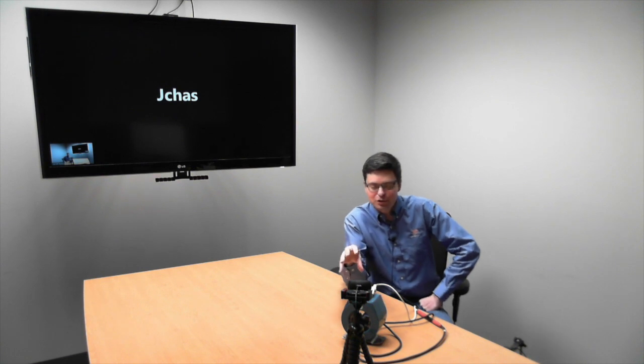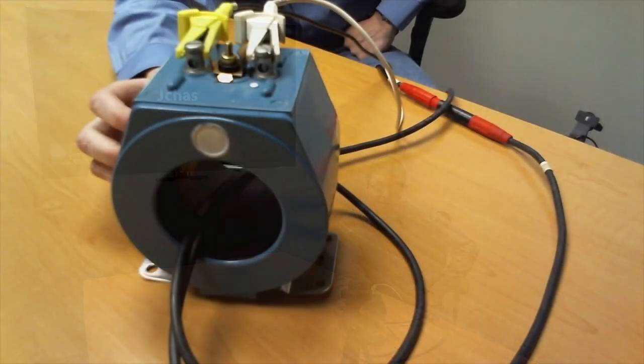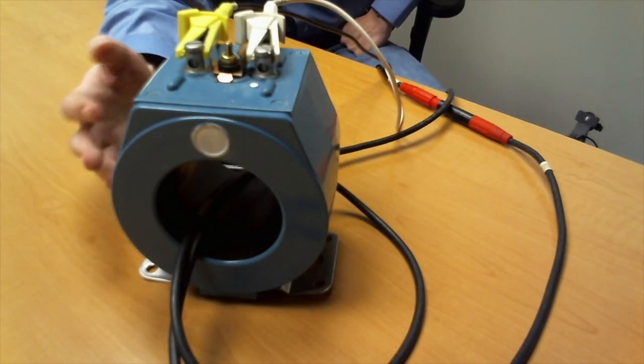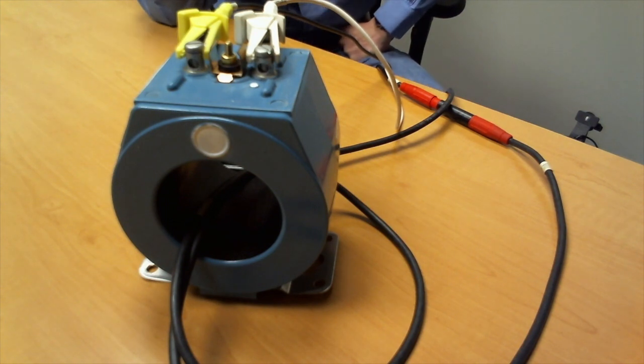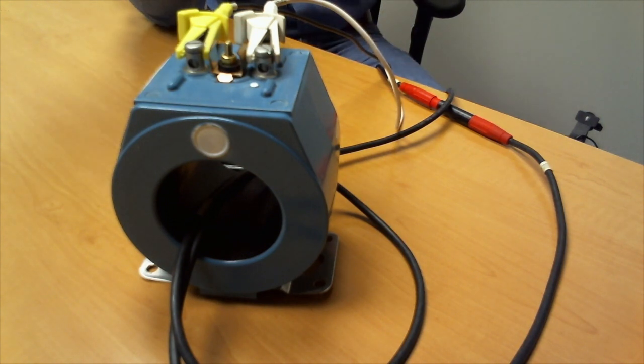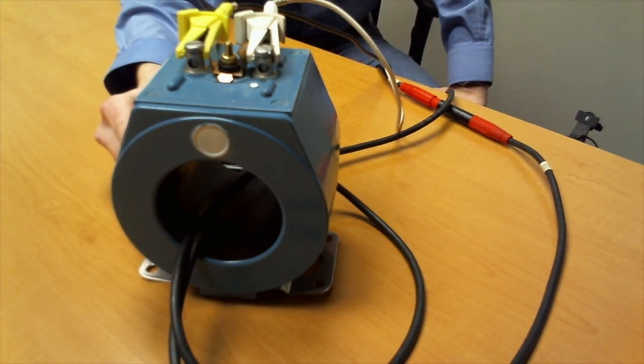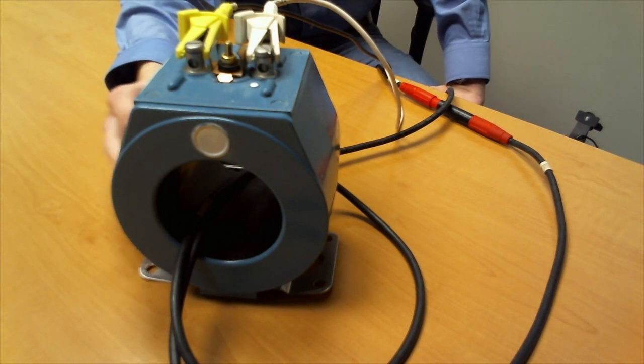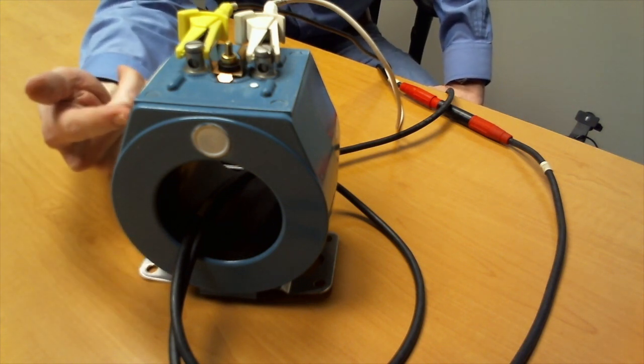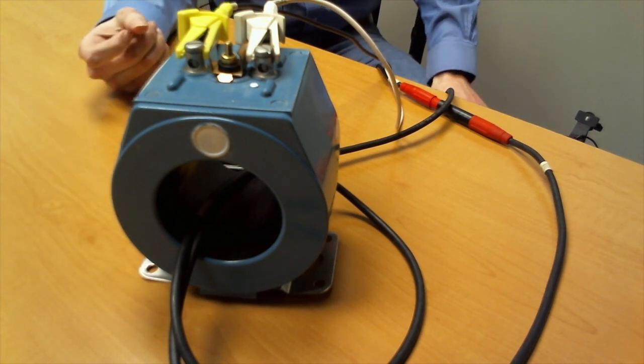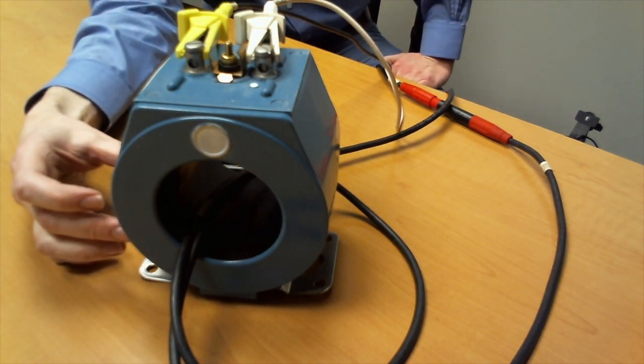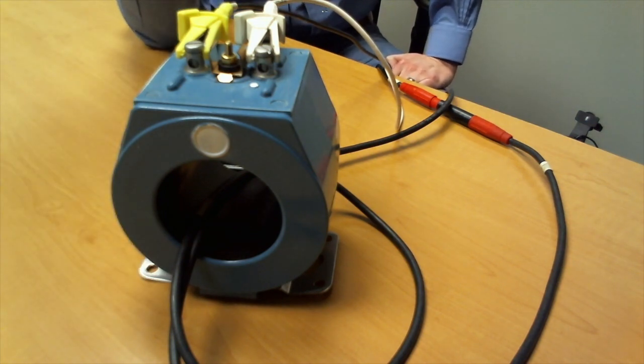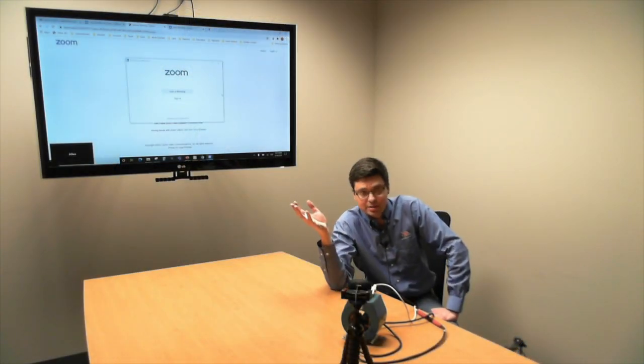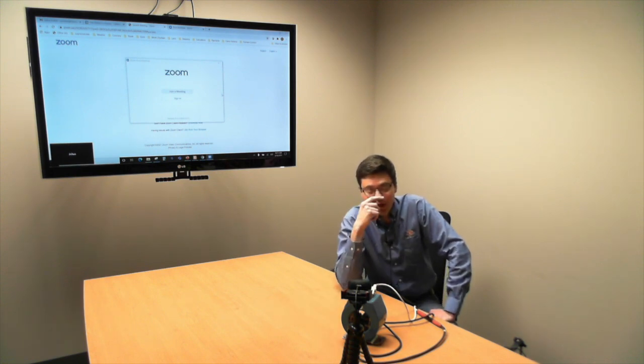So what I wanted to show was, this is the CT that Nick sent me. It's a 0.15S, that's the accuracy class he was talking about, extended range. And if you remember seeing on that chart, he said that can go all the way down to 4% of nameplate, all the way to the rating factor. So what he sent me was a 600:5 CT with a rating factor of 3. And the information I'm getting is all from this nameplate here on the side of the CT itself. And they also stamp the nameplate value on the side so you can easily see it when you've got inventory on the shelf. You can grab it, see it, or you can see it when it's in the cabinet or when it's mounted on the pole.